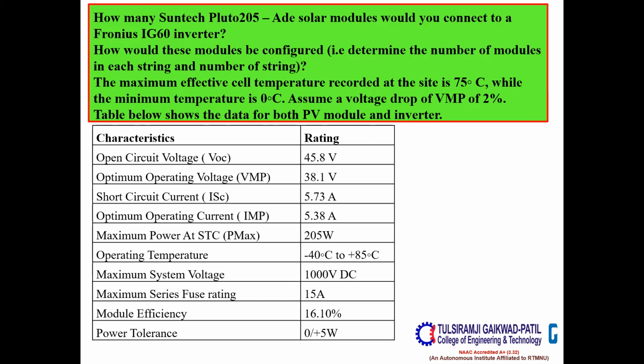Okay, so this is our problem statement. The problem we are identifying is: how many Suntech Pluto 205 ADE solar modules, the model of our solar PV module, would you connect to a Fronius IG60 inverter? How would these modules be configured? That is, determine the number of modules in each string and the number of strings. The maximum effective cell temperature recorded at the site is 75 degrees Celsius. We need to be very clear about what the maximum cell temperature would be at that particular site.